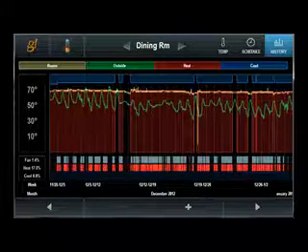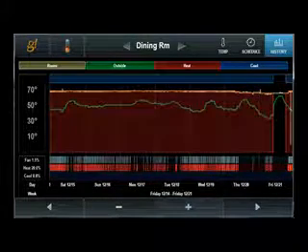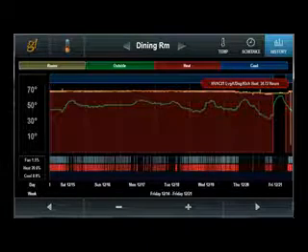Now another thing that he noticed is that in the weeks prior there had been painting done in the home. And this particular room has a 20-foot vault ceiling. So it's really high. And the painters came and took the air registers off and put them back on. But when they put them back on, they put them on upside down.